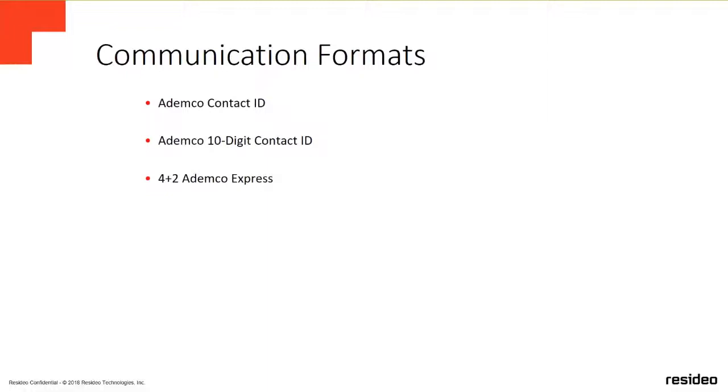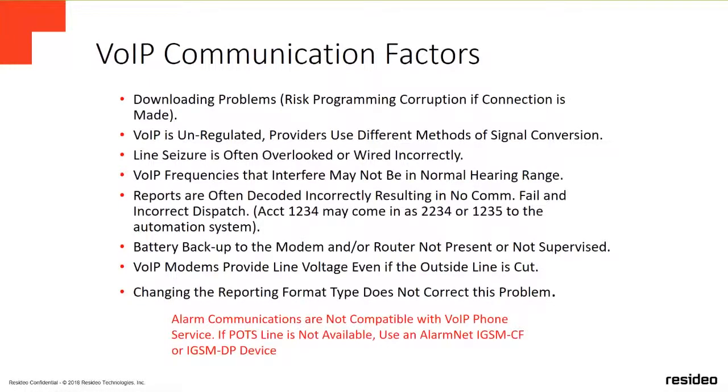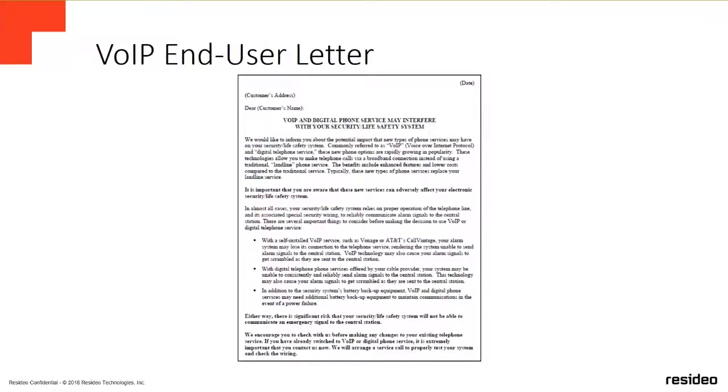The communication formats supported are Ademco Contact ID, Ademco 10-digit Contact ID, and 4+2 Ademco Express. Voice over IP phone lines are not compatible with Honeywell panels — alarm communication formats are not compatible with VoIP. You will need to use a network communicator or a third-party solution. Be aware that some third-party communicators behave as a phone line, and VoIP lines can give you wrong Contact ID formats and unstable signal delivery.